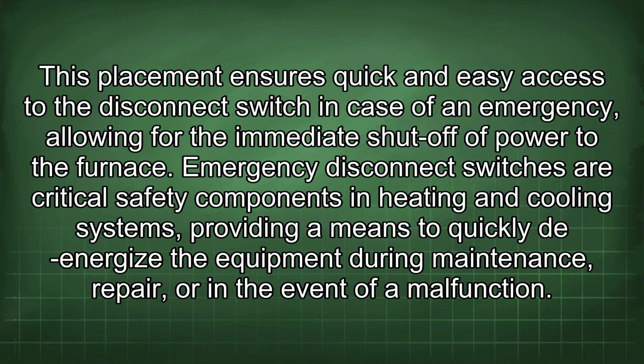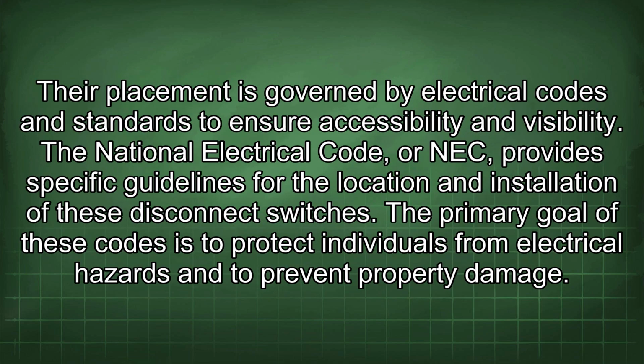Emergency disconnect switches are critical safety components in heating and cooling systems, providing a means to quickly de-energize the equipment during maintenance, repair, or in the event of a malfunction. Their placement is governed by electrical codes and standards to ensure accessibility and visibility. The National Electrical Code, or NEC, provides specific guidelines for the location and installation of these disconnect switches. The primary goal of these codes is to protect individuals from electrical hazards and to prevent property damage.